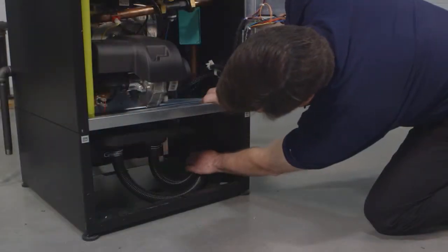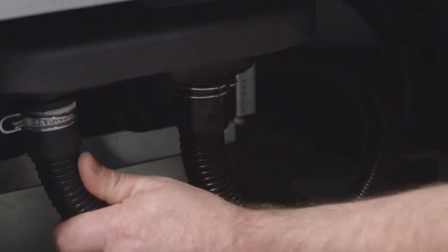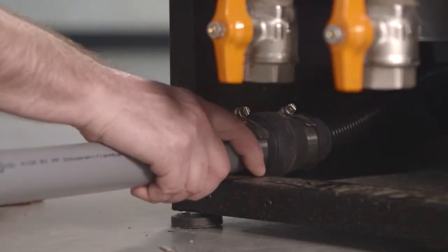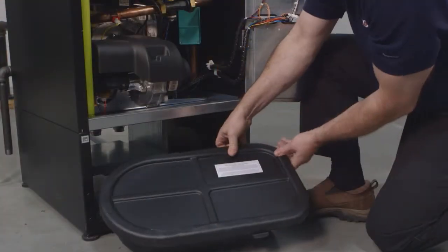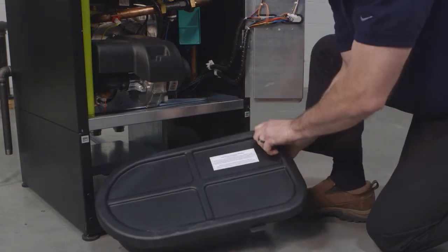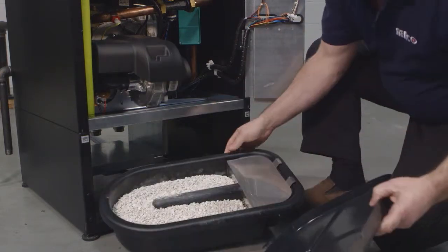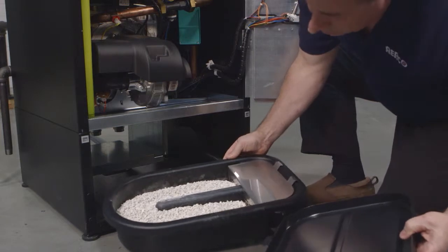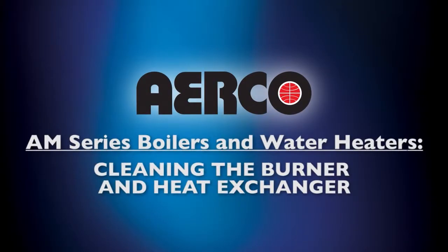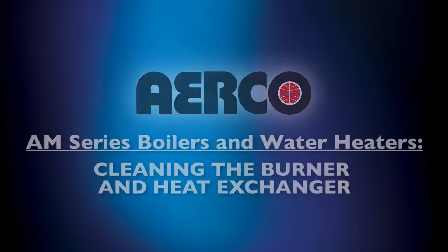Inspect the condensate drain lines, condensate fittings, and condensate trap for signs of weeping or leakage. Ensure there is sufficient neutralizer media. It is recommended to replace this media annually. The burner and heat exchanger must be checked every year and cleaned if required. Now we'll show you how.